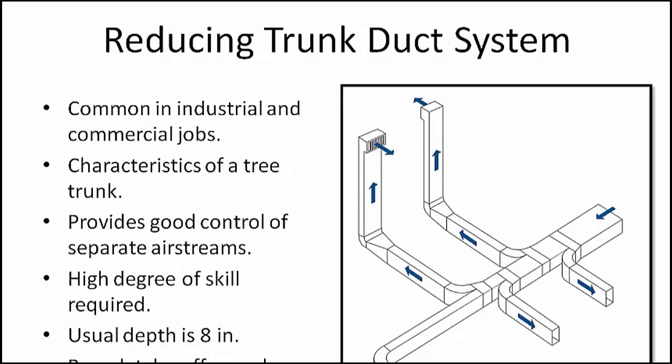The reducing trunk duct system maintains pressure from start to finish by reducing the size of the trunk duct as branch ducts are connected. Shown on this page, it is common in industrial and commercial installations and in some residential jobs. The main feature of this arrangement is that the system has the characteristics of a tree trunk — it is broad at the base and gradually gets smaller as the branches sprout. When properly designed and installed, a reducing trunk duct system provides good control of separate air streams and uses a minimum of sheet metal. Because of the many specially shaped fittings, installation cost is high and a high degree of skill is required of the sheet metal craftsman. Most of the duct work has to be built at a shop, with construction based on spot measurements made on the site and close tolerances.